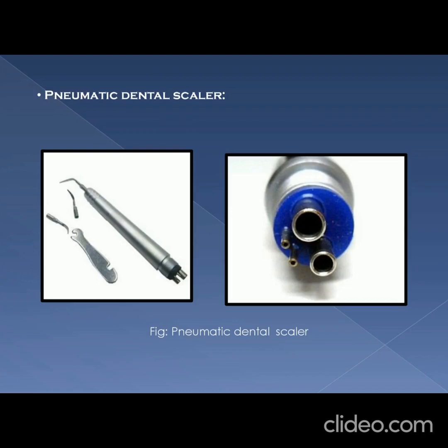Pneumatic scaler for fast and simple tartar removal. The instrument can be used on any unit in place of the turbine handpiece without requiring any additional adjustment. The scaler can be used for prophylaxis procedure or bone surgery with the aid of the range of KAVO and Comet inserts. The power of vibration can be adjusted with a rotating ring, making the prophylaxis more flexible and accurate. The scaler comes complete with 3 different inserts.